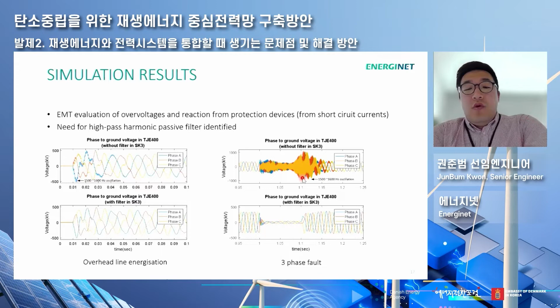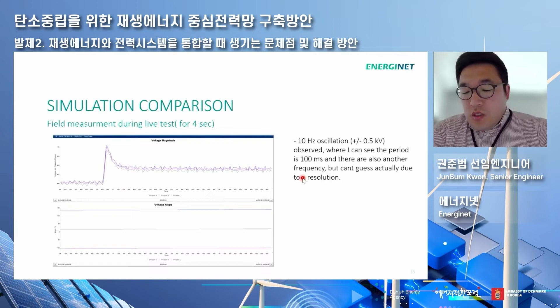This is the actual measurement we saw on the site. It's around 10 hertz oscillation, and we observed 10 hertz oscillation. We have various ways of analyzing this. Impedance-based analysis was used to simulate the impedance for the grid, to see if the actual oscillation is appropriate or detrimental.